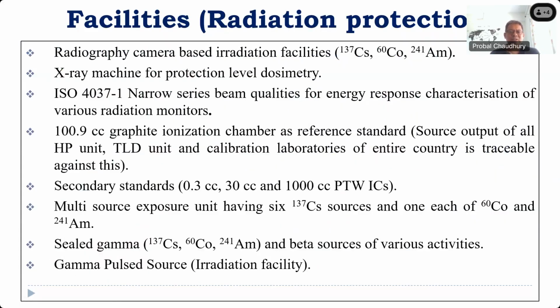Then, coming to the facilities for protection level instruments, we have a radiography camera based irradiation facility for different radionuclides like cesium-137, cobalt-60, and americium-241. And we have an X-ray machine for protection level dosimetry. And we have the ISO 4037 narrow series beam qualities for energy response characterization of various radiation monitors. Basically, for radiation monitors, you not only have to have the reading, you have to have the characterization for different energies. Generally, gamma energies vary from around 100 to 200 keV up to 2.5 to 2.6 MeV. So we have to cater to the entire range for carrying out the calibration.